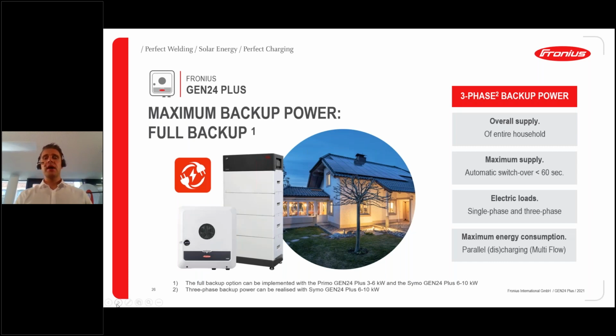10 kilowatts. You have got, of course, a maximum supply of the household, and you can also configure an automatic switchover. That means you need an additional installation, a switchover component at the feeding point, which takes approximately 30 to 60 seconds, where the customer detects this grid failure, and then the inverter builds up its own network. It is then the grid builder, and it supplies all loads within the household, so also single phase and three phase, and you can then also have the maximum energy consumption within your household.